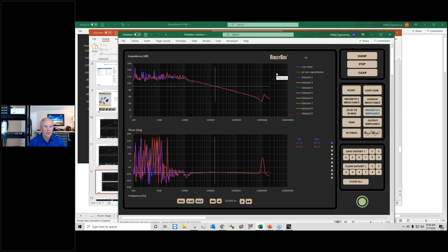And there you go, that's 47 picofarads, right below the transformer capacitance, primary to secondary. Remember, our primary to primary capacitance on this design was quite low, around 10 picofarads. Primary to secondary is about 44 picofarads on this design.